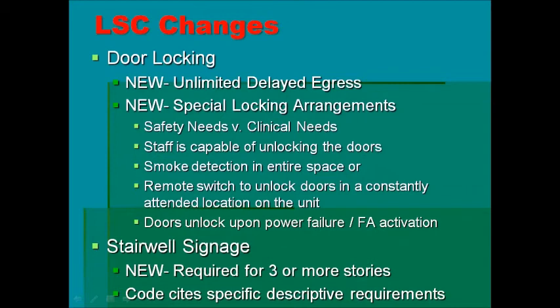In the past, special locking arrangements were only allowed for clinical purposes within a healthcare facility, meaning there was a medical diagnosis or reason why you needed to have people locked in a certain unit, a secure unit. NFPA and CMS have broadened the interpretation of that to now include the safety needs of the occupants of a facility. So if you can make a case that you need to put a special locking arrangement like a delayed egress locking device or an access control device on a unit, you can justify it not only for clinical needs but for safety needs as well. Of course, there are several fail-safe elements that you need to make sure of on these arrangements, that they release with the alarm, that they release with power failure, and so on and so forth.